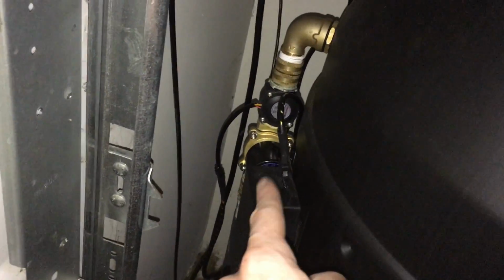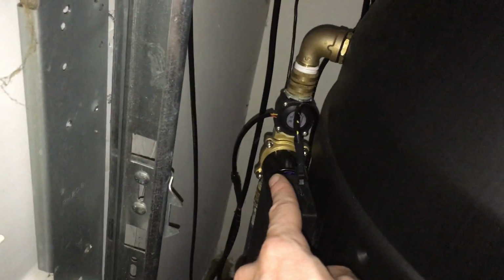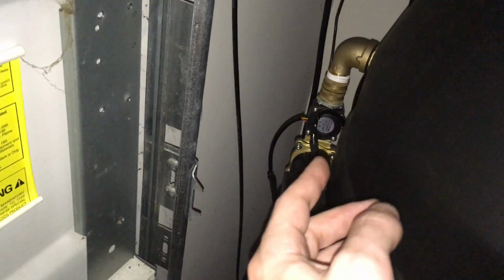You'll notice that is after the valve, which basically controls the logic for filling up. The reason is because you don't want to apply all the pressure that may be coming from a hose line onto the flow meter. You want that pressure onto the valve, and then you want the meter to be monitoring anything that comes after that. So that's the in meter for measuring flow.